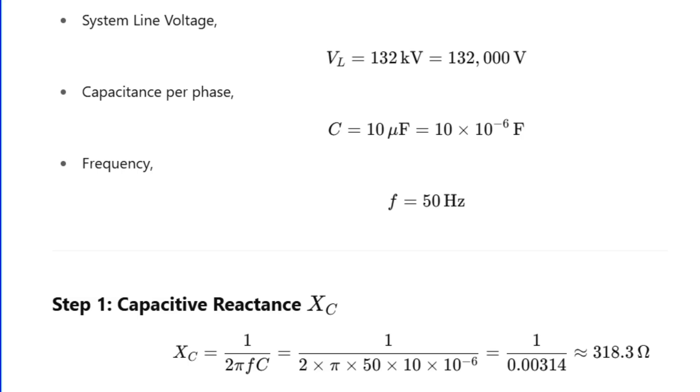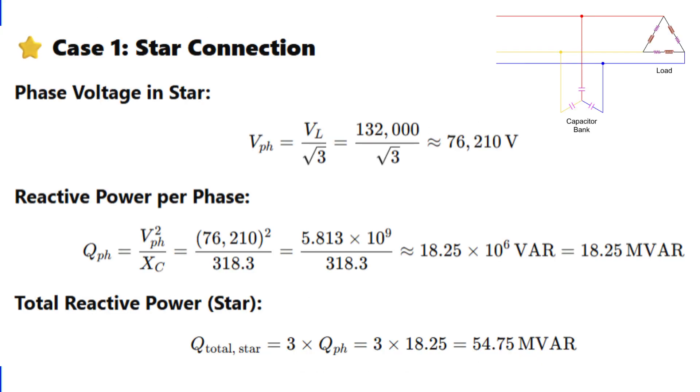In a star connection, each capacitor is connected from phase to neutral, so the phase voltage will be line voltage divided by root 3, that is 132,000 volts divided by root 3, which comes out to approximately 76,210 volts. Now reactive power per phase is V squared divided by XC, that is 76,210 squared divided by 318.3, which gives approximately 18.25 megavolt-ampere per phase. Multiply that by 3 for the total: 18.25 times 3 gives 54.75 megavolt-ampere reactive in star connection.